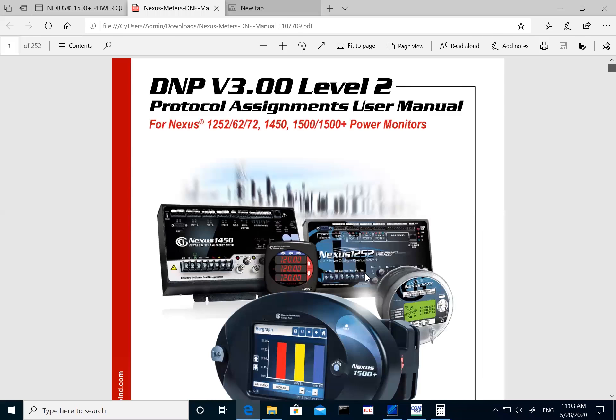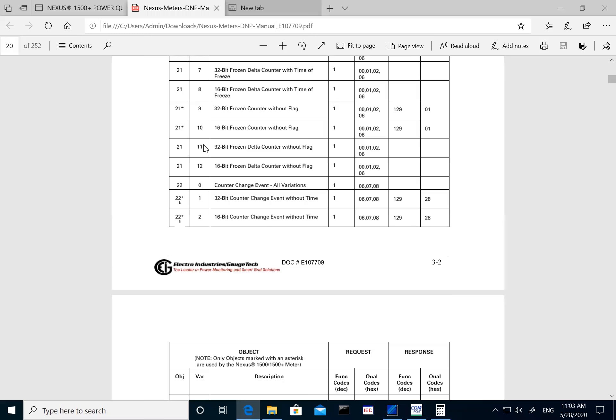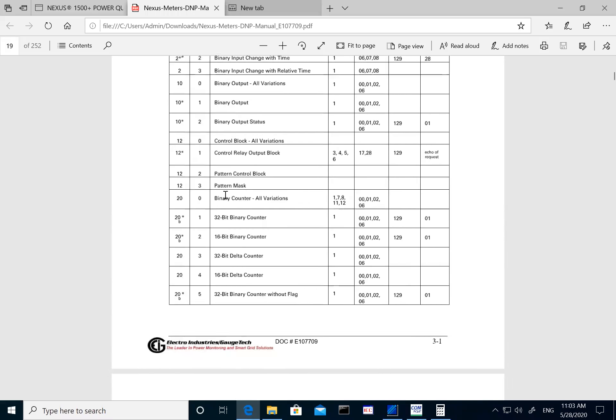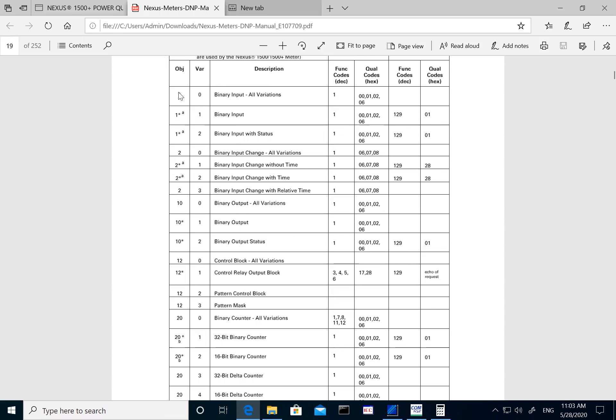We talked about the different functions that the meter supports on the DNP side. The way the DNP protocol works is that all your parameters — typically voltage, current, power, energy — are segregated or grouped into different classes. You have class 0 and class one, two, three. You can define your own parameters for each class. Along with this, there are also objects in DNP.